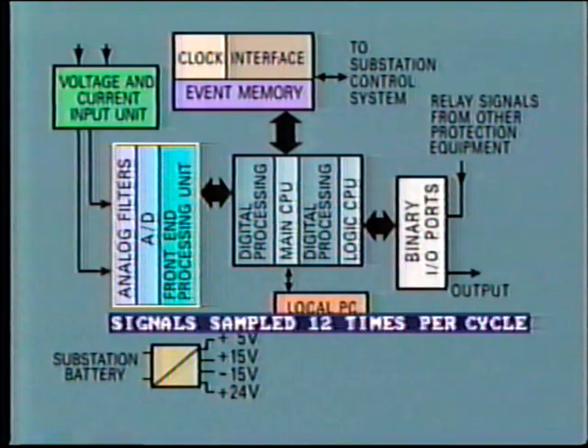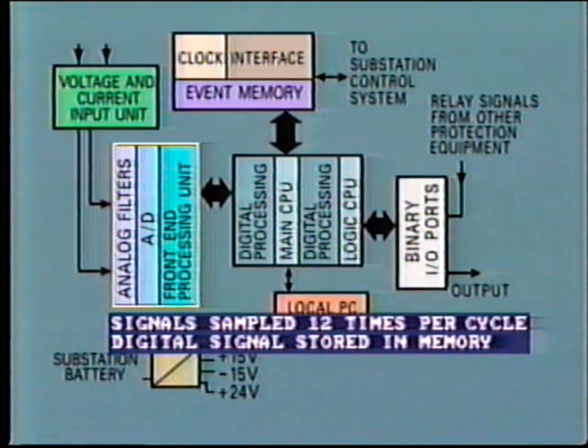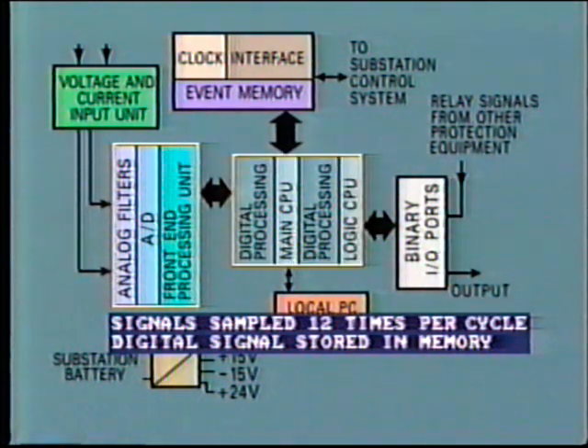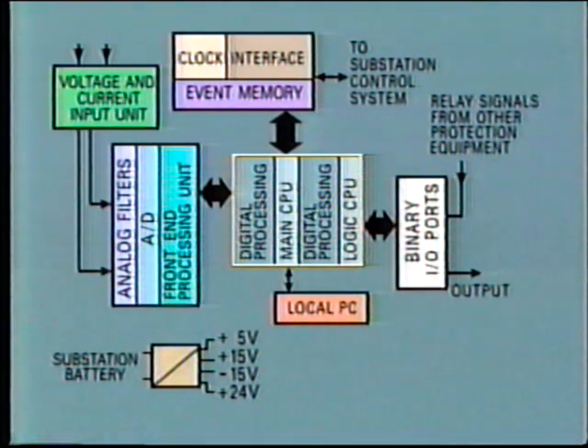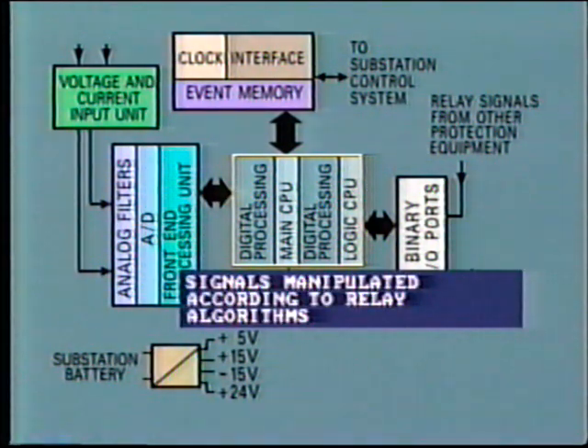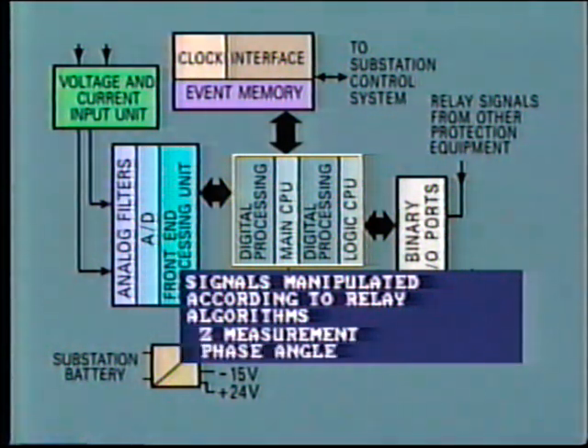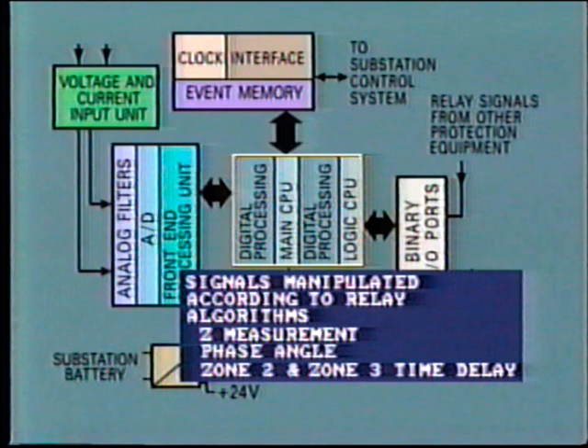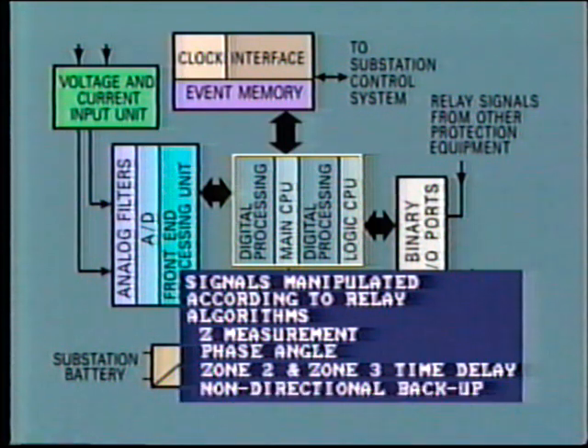Each of these signals, 7 in our hypothetical example, is sampled, say, 12 times per cycle, and the corresponding digital value is stored in the memory until accessed by the main processing unit. Here in the main processor, these signals are recalled and manipulated according to the relay algorithms. In this particular relay, this will provide impedance measurement, phase angle, Zone 2 and Zone 3 time delay, non-directional backup, etc. The algorithm can be arranged to provide all of the functions that we are accustomed to and more.